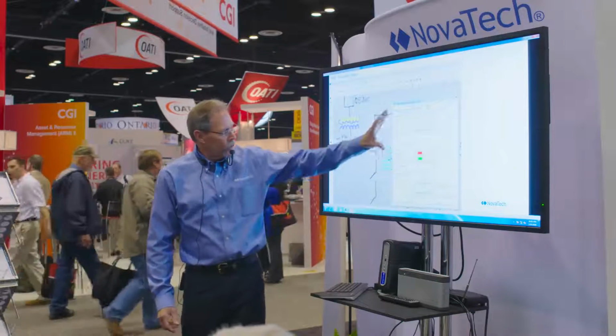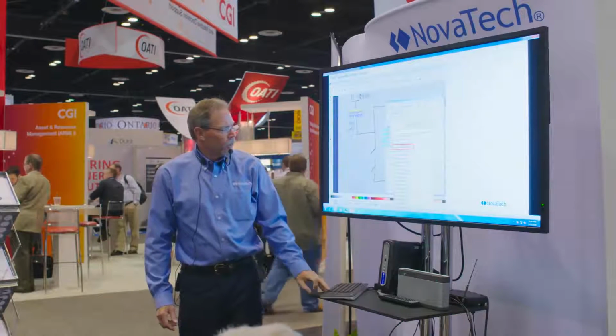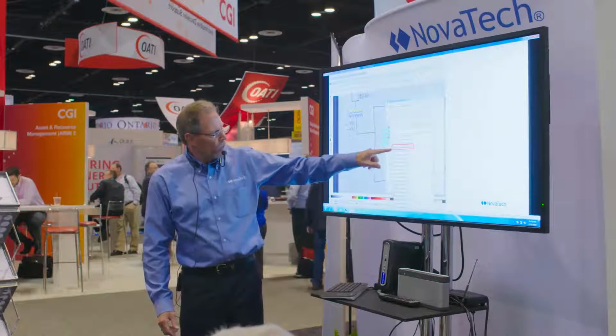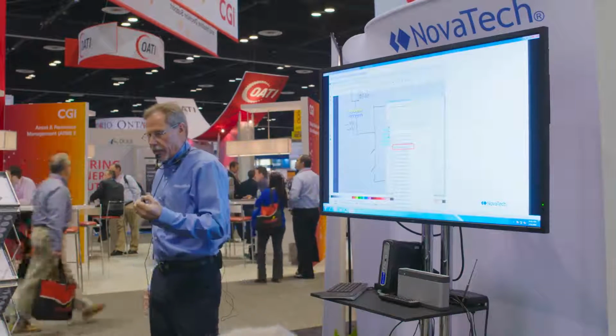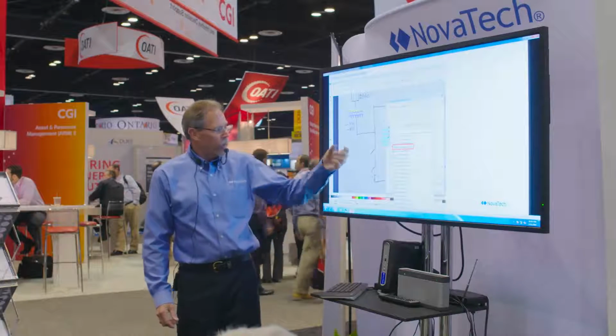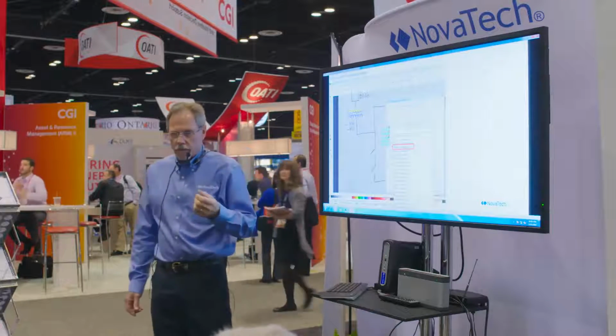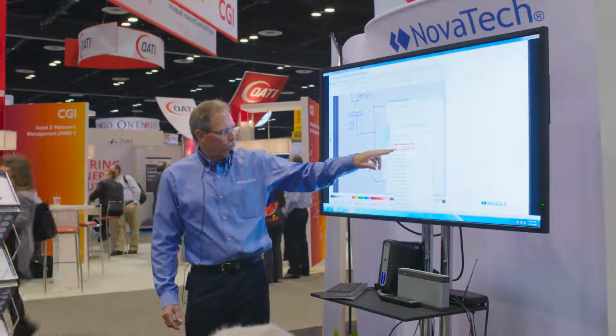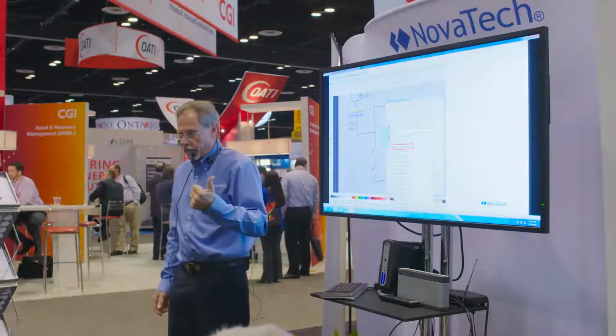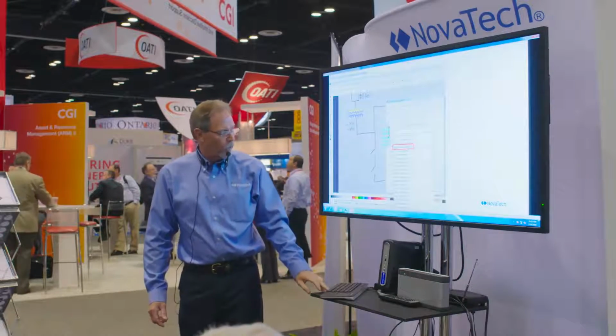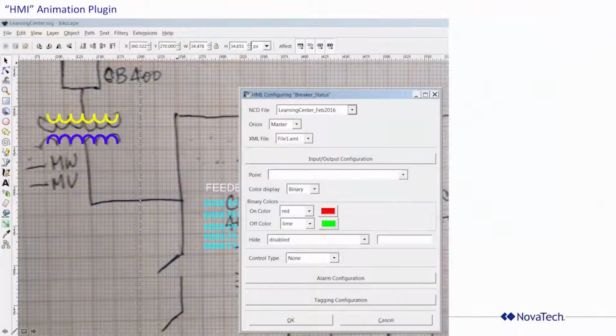So when I select that, this is what pops up. I go into my drop-down menu and pick out what point in that database I want that object to operate on. So when input 1 on this particular device goes high, what's the color going to be — red, or green? This is where I make my selection based on that binary input's state.